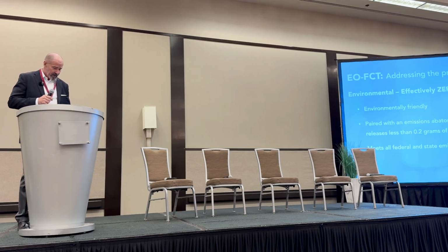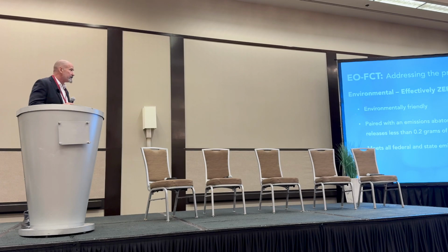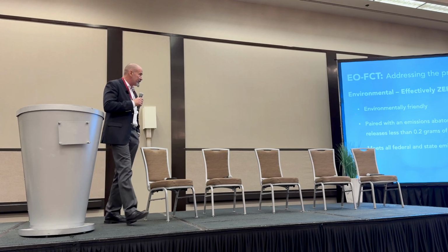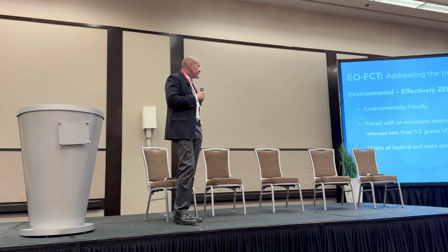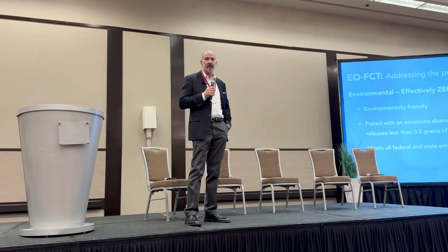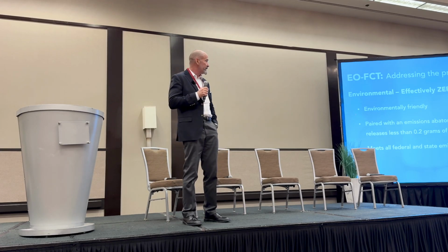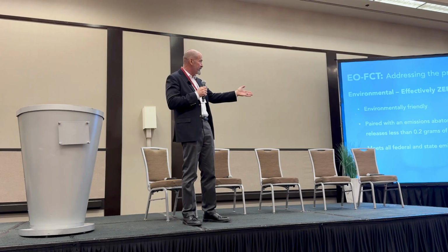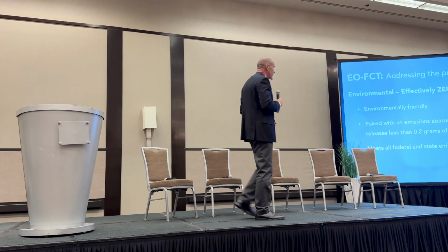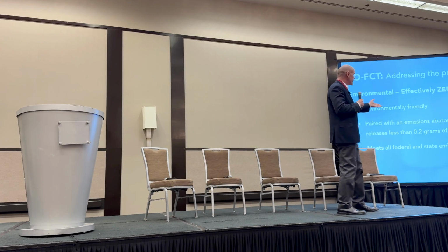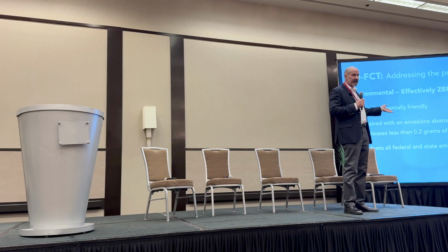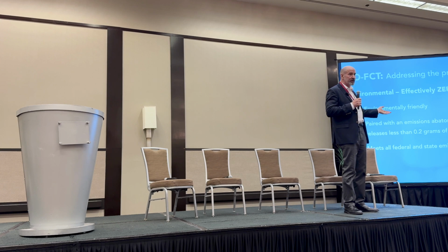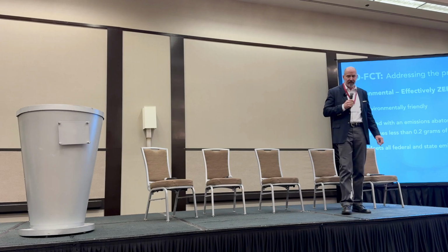Now, environmental. We've been calling this a zero emission system. In fact, we are releasing a fraction of a gram of ethylene oxide per cycle when you use one of our abaters. Because we're using so little gas, we're able to use a very simple dry bed technology. It's a dry resin bed. There is no potential ignition source, and it's very, very effective.